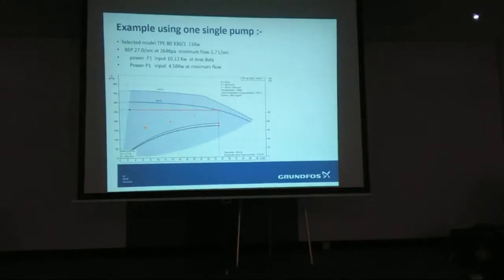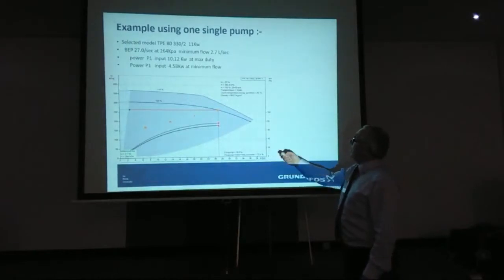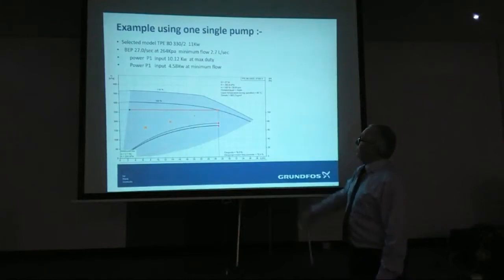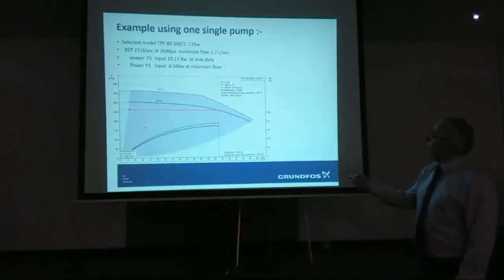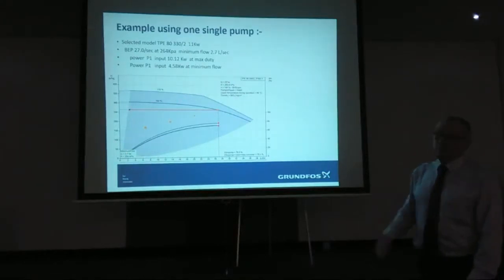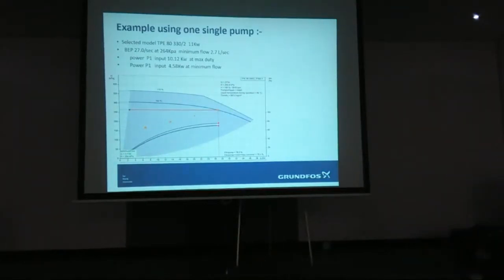And so a pump performance curve would look something like this. This is one taken off our product centre. This could be anybody's pump, any manufacturer, just happens to be Grundfos because I've worked there. So this is the best efficiency point here: 27 litres a second, whatever that is, 264 kPa. So therefore, that one will be roughly 2.7 litres a second. Most heating systems I've come across, particularly HRUs, 2.7 is too much. But that pump would do that nicely.